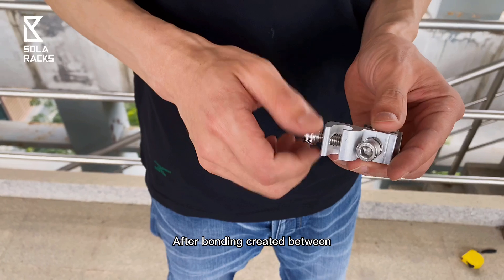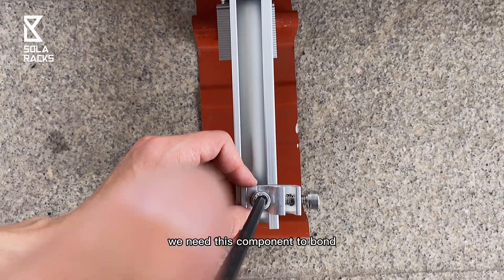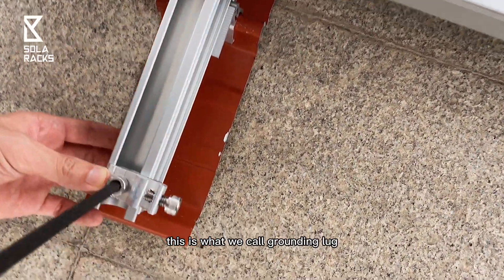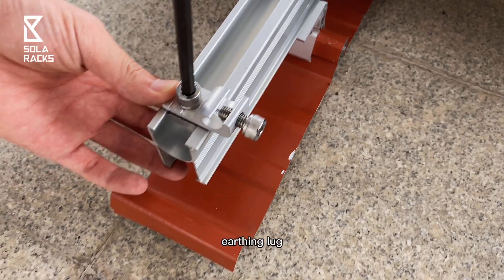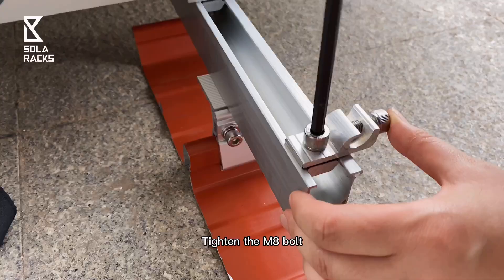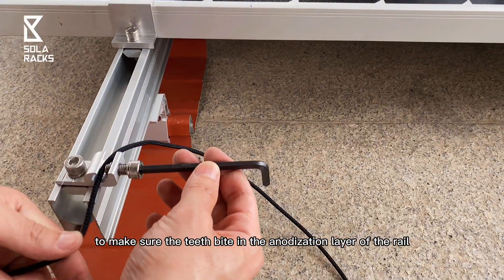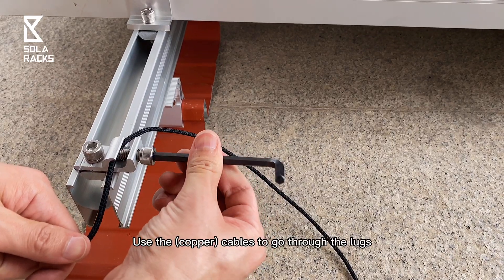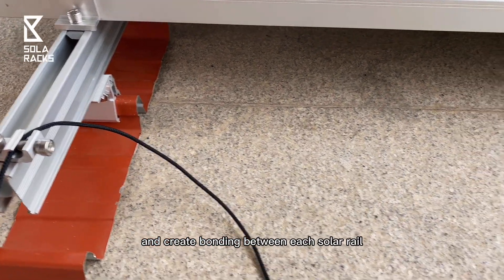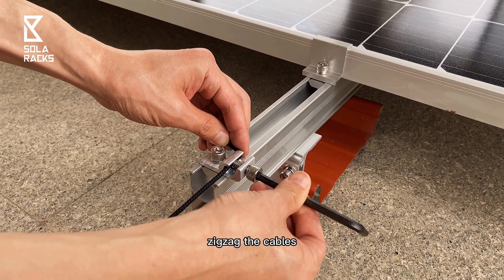After the bonding is created between the solar panel and the mounting structures, we need these components to bond all the PV array to the ground. This is what we call the grounding lug, or earthing lug. Tighten the M8 bolt to make sure the teeth bite into the anodization layer of the rail. Use the cables to go through the lug and create bonding between each solar rail. Installers like to zigzag the cables.